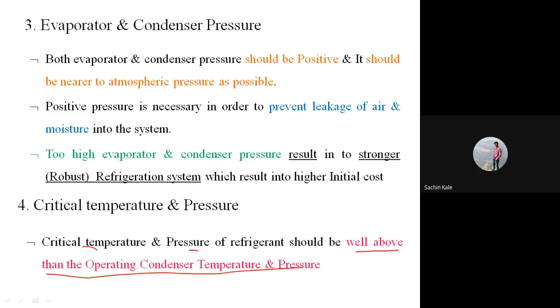So while selecting any refrigerant for a particular application depending upon critical temperature and critical pressure, we have to select that refrigerant in such a way that the critical temperature and critical pressure of that refrigerant should be well above the operating condenser temperature and pressure. So that is the parameter called the critical temperature and pressure.